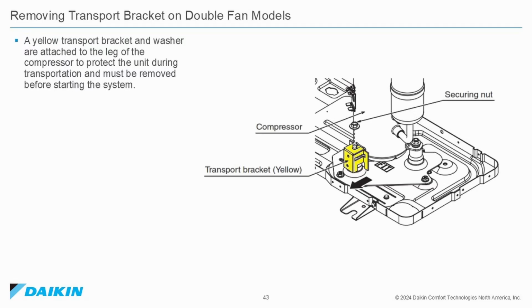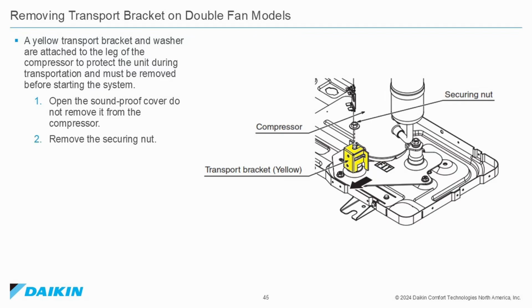Removing the transport bracket on double fan models. A yellow transport bracket and washer are attached to the leg of the compressor to protect the unit during transportation and must be removed before starting the system. Open the soundproof cover that is wrapped around the compressor, but do not remove it from the compressor. Remove the securing nut. Remove the transport bracket as shown in the diagram.